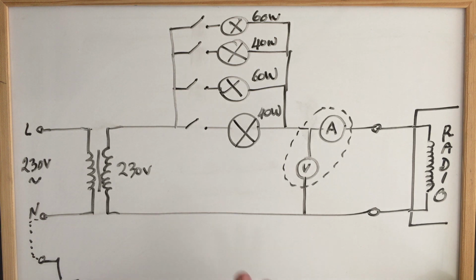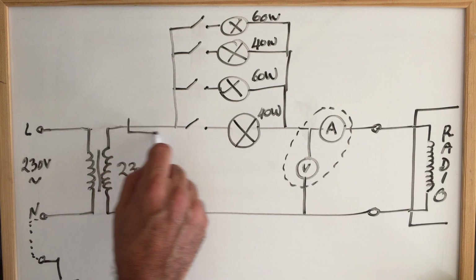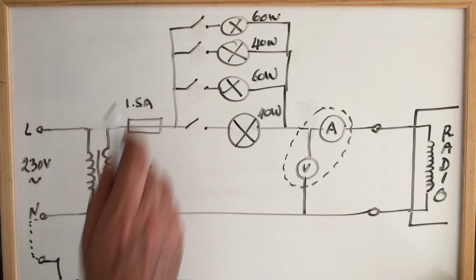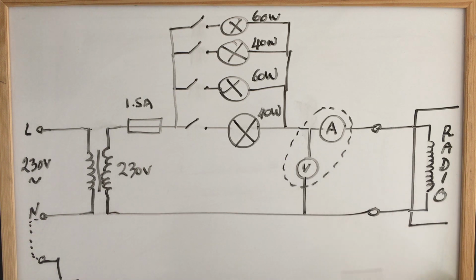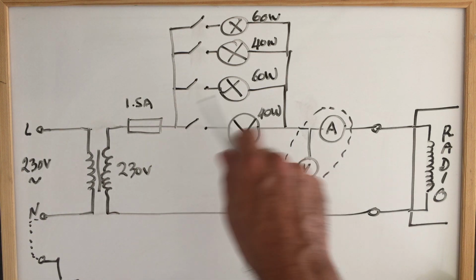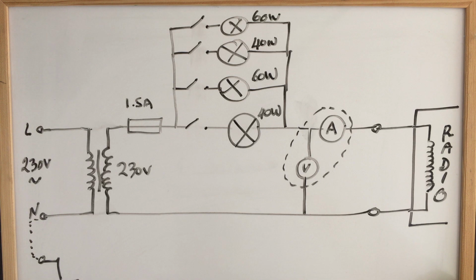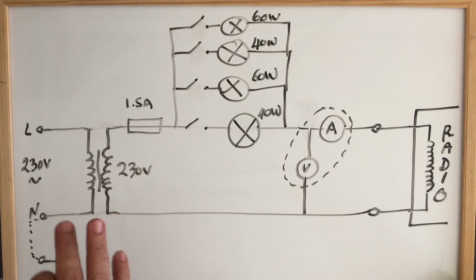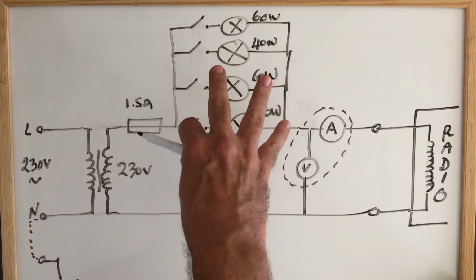The other thing here is to prevent this from overloading. I'll put in a fuse, 1.5 amps. So if there is a short and this thing blows through, I've got that limited to protect my transformer. Because this is an isolation transformer, and I sometimes just want to benefit from the isolation function without the limiting function, I've added a switch here.